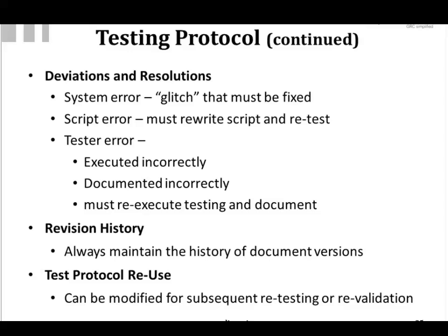And you'll have a deviation log attached to your test scripts that will show each deviation uniquely identified, what was the purpose, what was the actual issue, what was the root cause, what was the resolution to it, and confirming that you were able to continue testing.